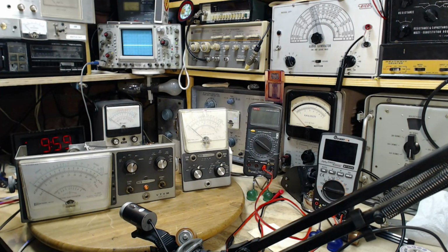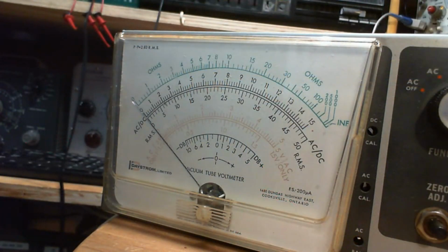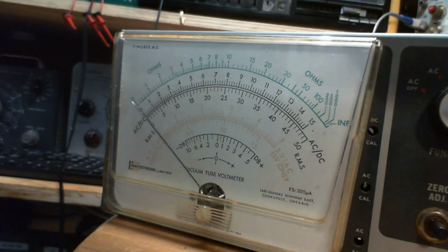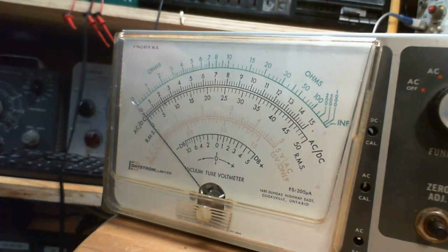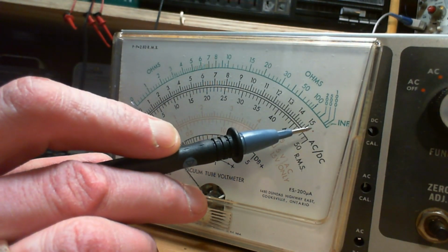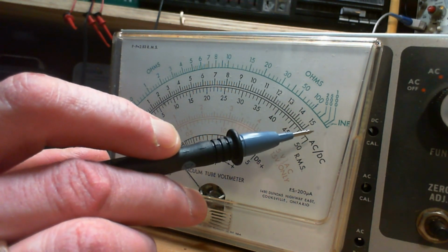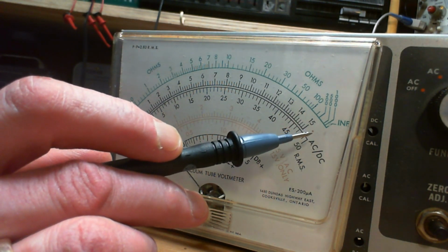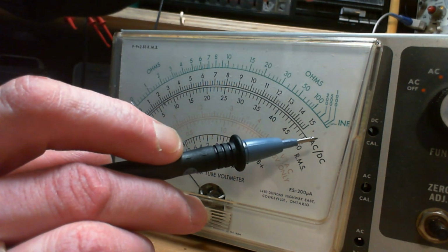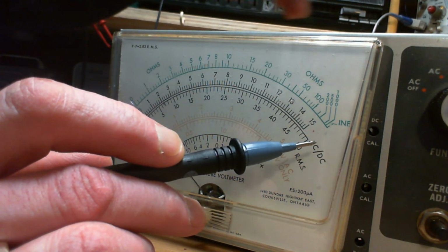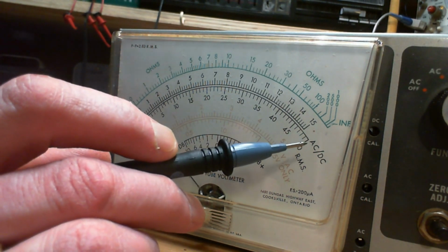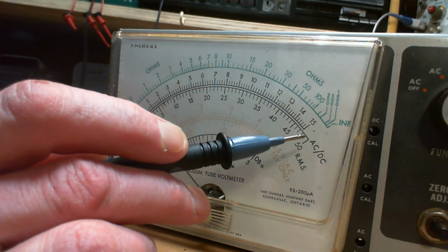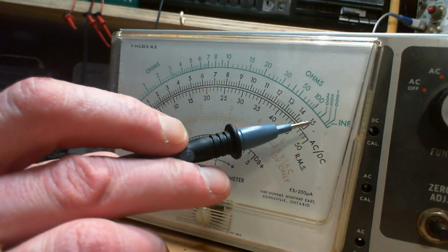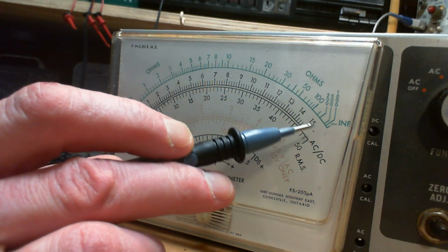Okay, so red dot. Let me get it on the close-up camera here because you'll never see it with the far camera. The red dot we are aiming for is right here, right there. So it's saying hook up a 1.5 volt battery. You actually use the one that's in the machine up here, but it's not in there right now. The battery that drives the ohm meter readings. Utilize that battery and set this meter to read there.